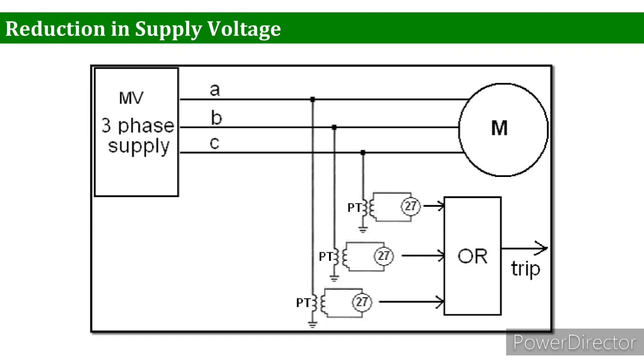The other one is the reduction in supply voltages. The torque developed by an induction motor is proportional to the square of the applied voltage. This is the basic concept we have about motors. Therefore, any reduction in supply voltage has a marked effect on the developed torque. The reduced torque may cause the motor to draw more current. Under voltage release may be used for protection against the reduced supply voltage. So for an LV motor there is no need for PTs.